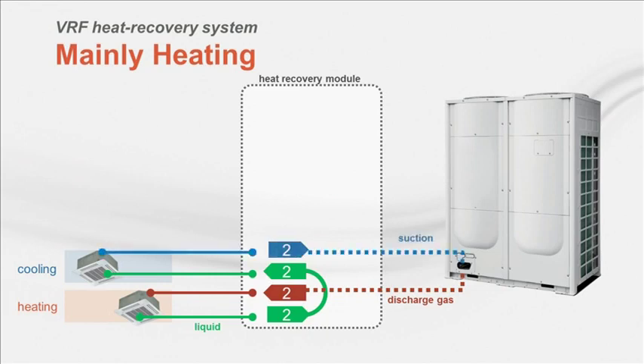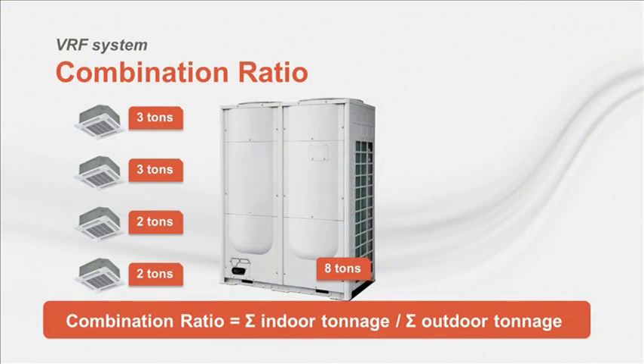After evaporating in the indoor unit that needs the cooling, 2 tons of suction gas is returned to the heat recovery control module and back to the outdoor unit. We have converted 2 tons of discharge gas to heating and used its condensed liquid for 2 tons of cooling. So 4 tons of benefit for 2 tons of energy. This is also an opportunity to introduce another characteristic of a VRF system, commonly referred to as combination ratio. The combination ratio is the sum of the indoor tonnages divided by the sum of the connected outdoor unit tonnages. The maximum this ratio can be is dependent on manufacturer, but is in the range of 1.2 to 1.5.